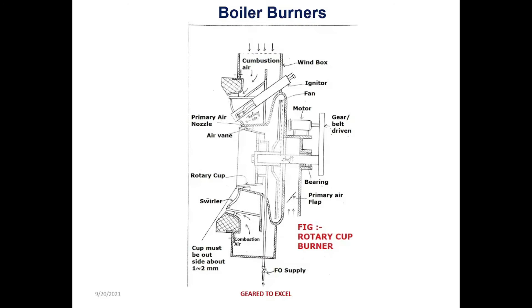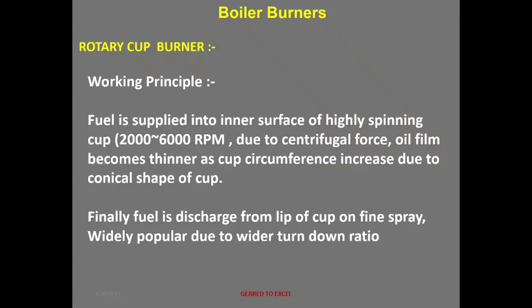Working principle of the rotary cup burner: fuel is supplied onto the inner surface of a highly spinning cup rotating at 2,000 to 6,000 RPM. Due to centrifugal force, the oil film becomes thinner as the cup circumference increases because of its conical shape. Finally, fuel is discharged from the lip of the cup as a fine spray. This burner is widely popular due to its wider turndown ratio.